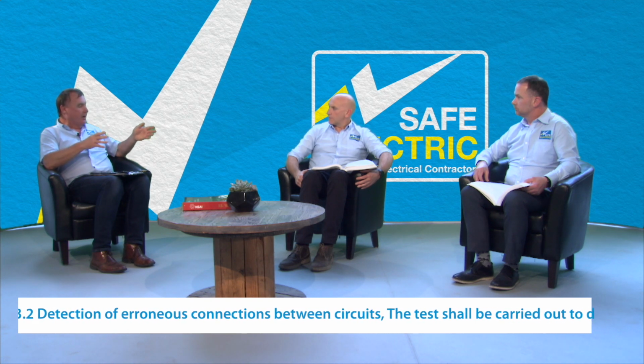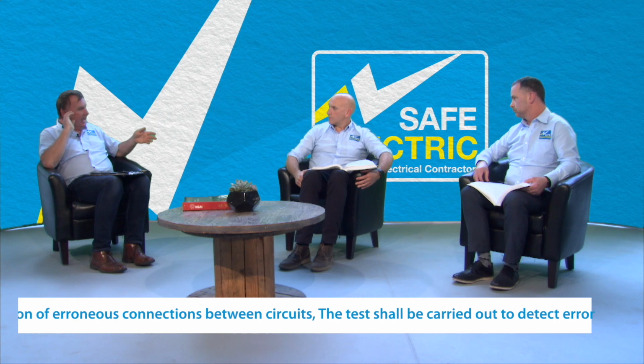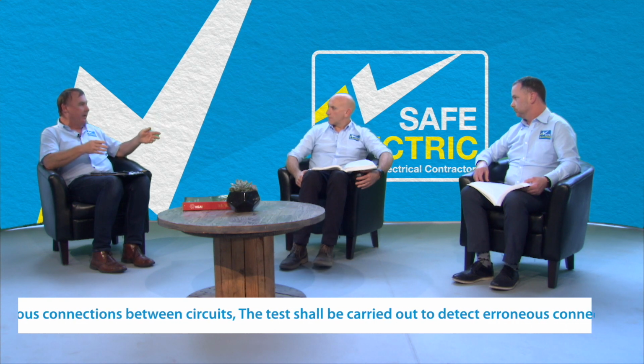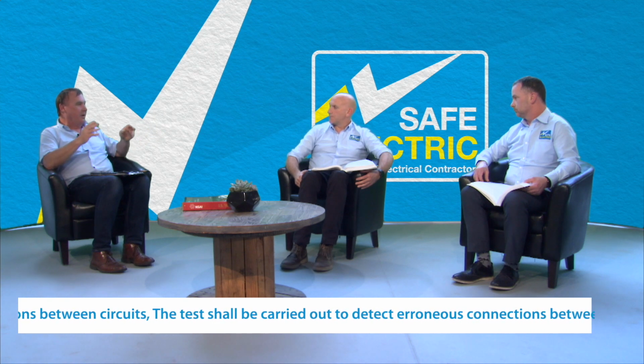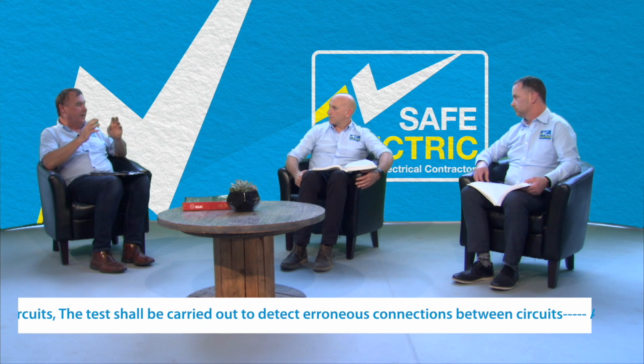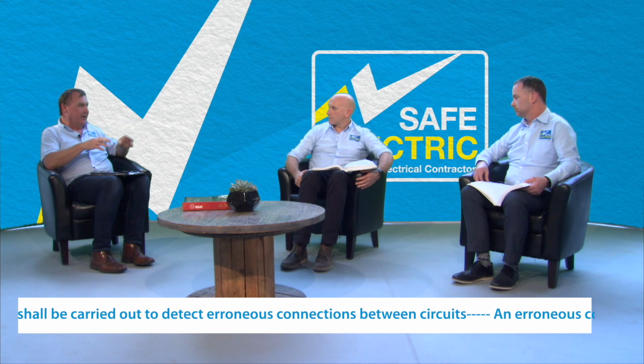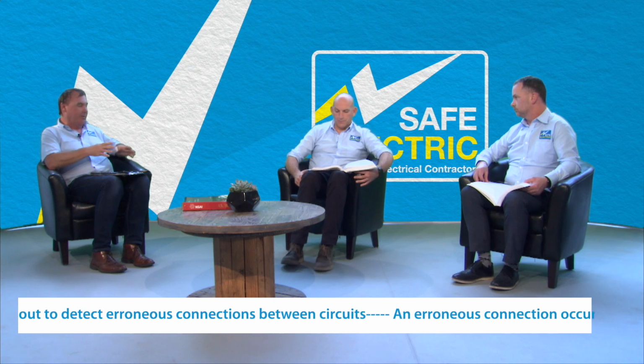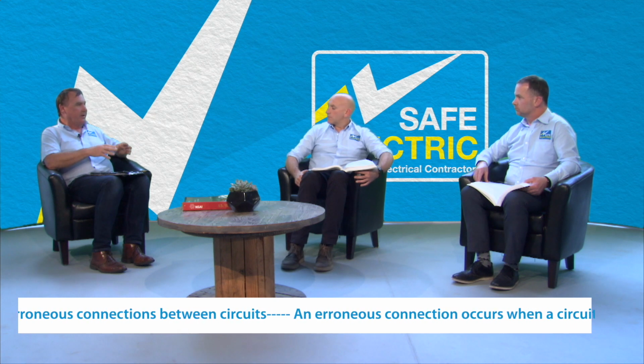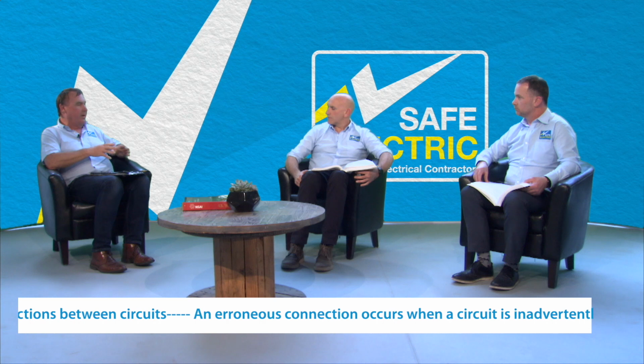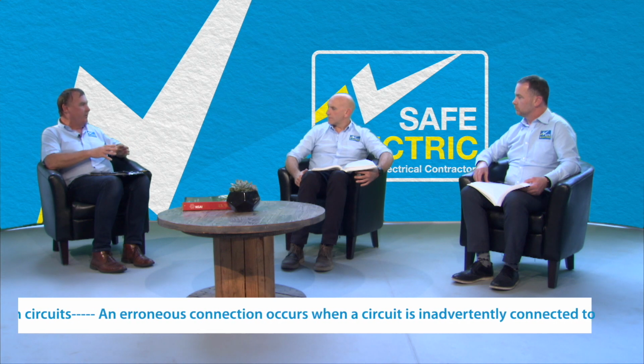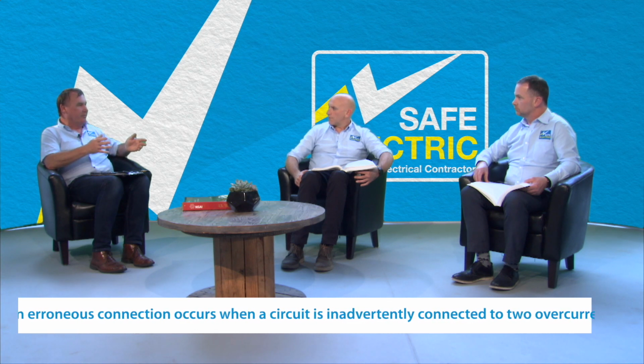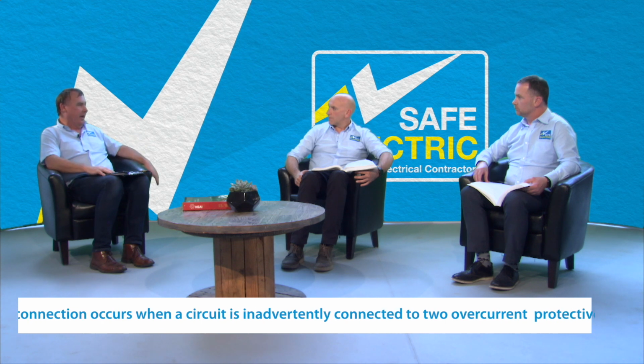Some contractors have the perception that you can't have the erroneous test if you didn't use a ring main. That is an incorrect perception. The erroneous fault can be in any electrical installation. So it's a very important test. And what we're checking for is that each circuit is independently fed from one fuse or MCB and one fuse or MCB only. And using the voltage test, we can easily determine that.